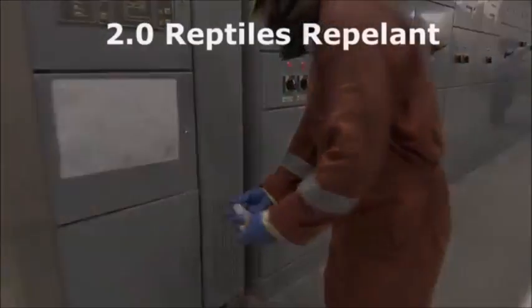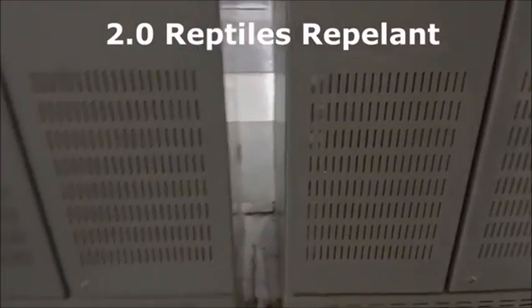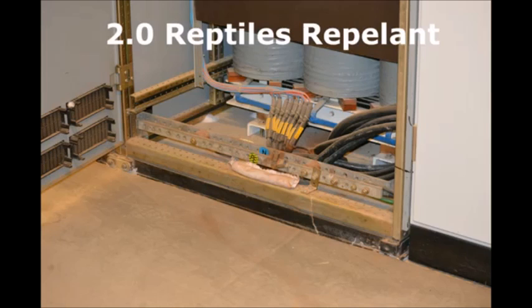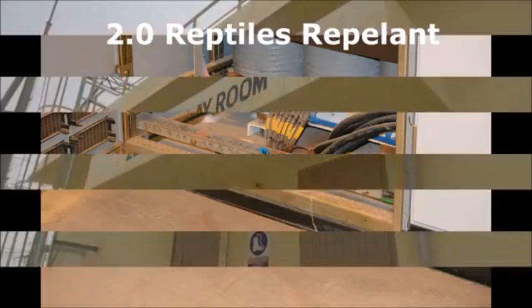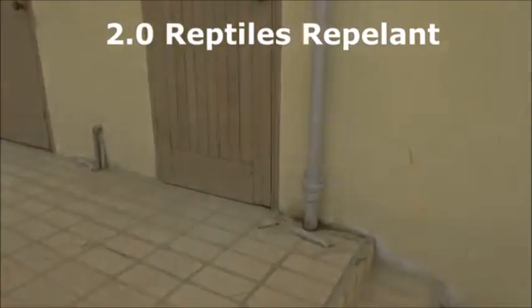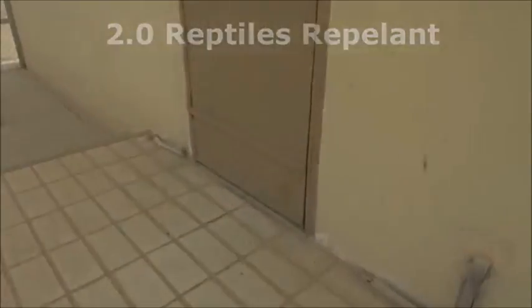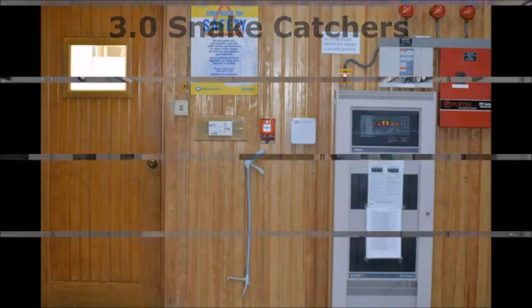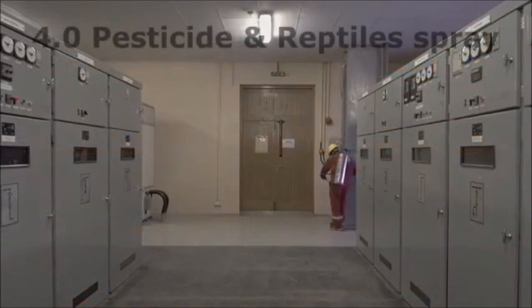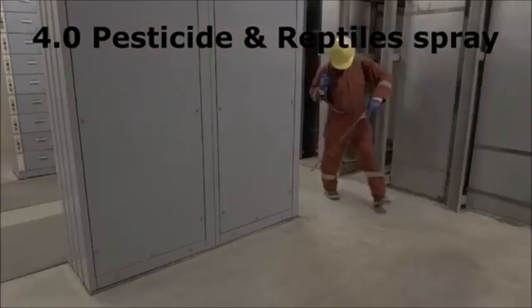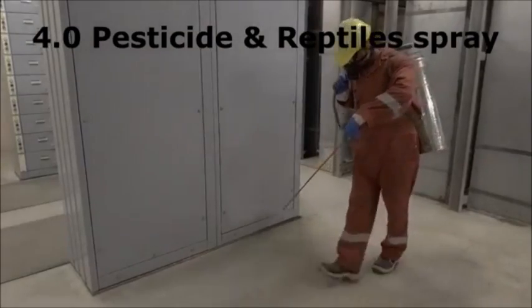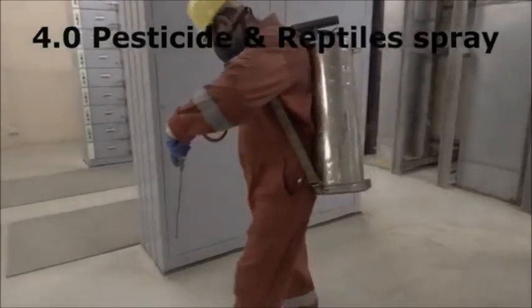Reptile repellent material was placed under breakers' cubicles and between electrical panels. It was also placed all around the cable conduit openings, including cable trenches, doors of 220 kV relay rooms, switchgear rooms and 6.3 kV breaker rooms. Snake catchers were placed at all necessary plant locations. Pesticide and reptile control spray is done at regular intervals, especially before and after the hibernating periods and at the beginning of summer.